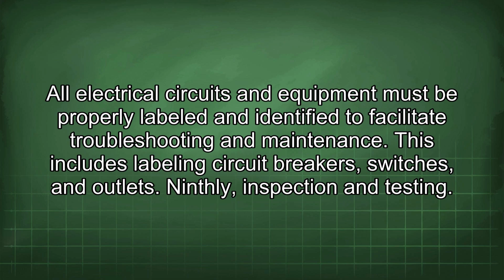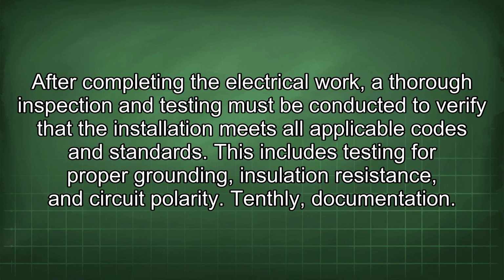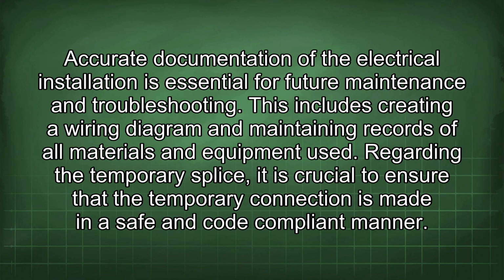Ninthly, inspection and testing. After completing the electrical work, a thorough inspection and testing must be conducted to verify that the installation meets all applicable codes and standards. This includes testing for proper grounding, insulation resistance, and circuit polarity. Tenthly, documentation. Accurate documentation of the electrical installation is essential for future maintenance and troubleshooting. This includes creating a wiring diagram and maintaining records of all materials and equipment used.